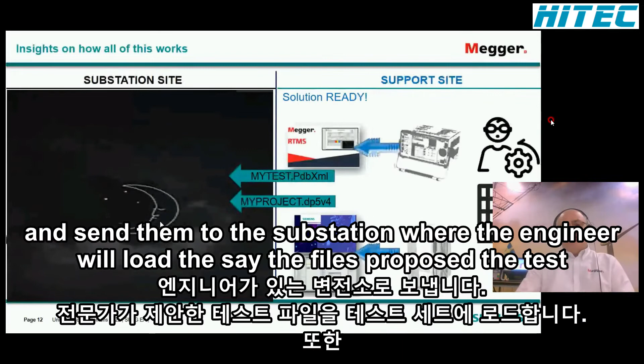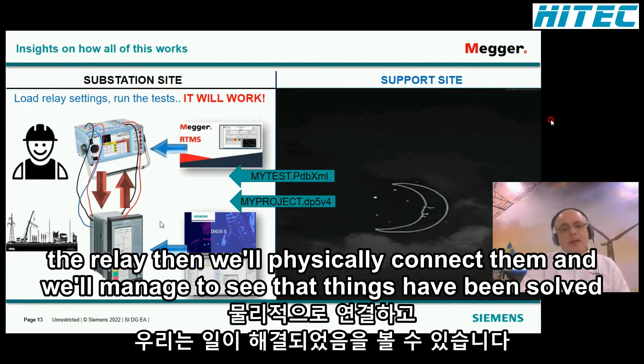Since we share the same data - which is key to the digital twin concept - we take these files and send them to the substation, where the engineer loads the proposed test files into the test set and loads the setting configuration into the relay. Then he physically connects them and confirms that things have been solved.